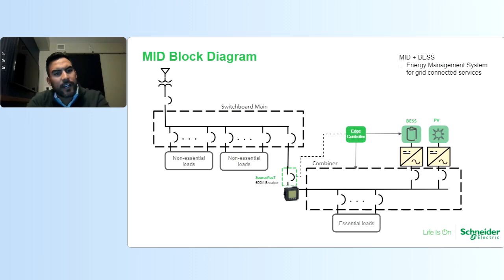And this is the block diagram that we like to show. It's like a reference architecture. So if you're considering designing with an energy storage system, this would be the ideal scenario where you have your main switchboard. Downstream of your main switchboard, you'll have this SourcePacT or microgrid interconnection device. And then you'll have this combiner panel or critical panel board where you have your essential loads already connected. This keeps, again, the equipment standardized.